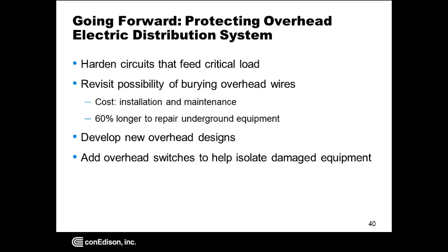We're looking at new overhead designs. One thing we're looking at is a special breakaway connector for house service at the pole end, so that if a tree branch falls on the service, instead of pulling it away from the house or pulling the pole over, the connector would break and allow the service wire, which would be de-energized at that point, to fall without causing further damage. We're also looking at things like spacer cable for locations with heavy foliage, and we're developing and installing new overhead switches to help isolate damaged equipment.